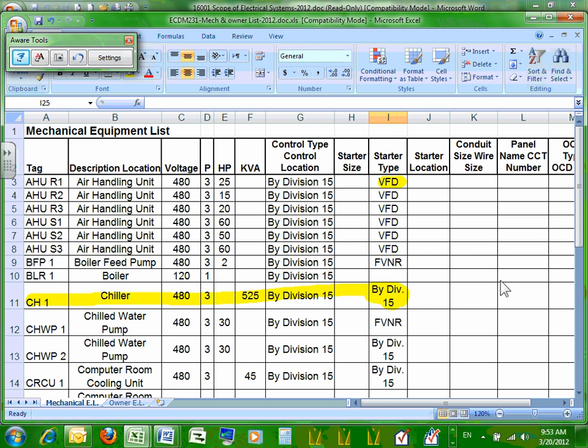When I'm modeling my power distribution system, I'm going to need to get cut sheets from my mechanical counterpart saying, give me the cut sheet on your chiller, show me what VFD you're using. What type of VFD is it, a 6 pulse, 12 pulse, 18 pulse, what do you got? Because that all changes the harmonic reflection into my system. So I have to get that information and model it in Power Tools. But it doesn't make sense for me to try to provide that VFD for the packaged equipment.